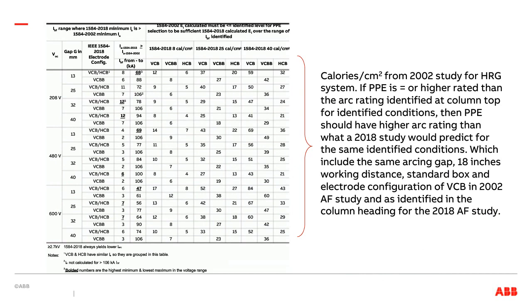So if you have a table like this, you essentially can take any situation and say, if my previous worst energy for this task based on the 2002 study was 5 calories, and I now have decided I have an HCB situation, and I have 8 calorie PPE, that's good enough. But if my previous calculation was more than 5 calories, then the PPE might not be good enough, and I need to do an actual arc flash calculation or go to the next level of PPE, which tells me that from 5, I now have up to 15. And if my calculation before was 15 or below, then I can use 25 calorie PPE. If my old calculation was 25 or below, I can use 40 calorie PPE.